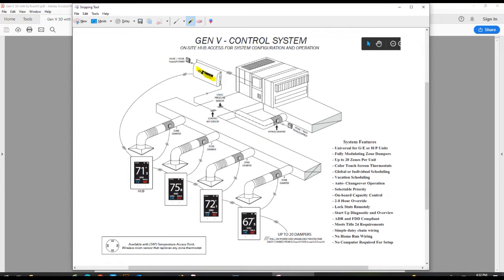Your Gen V control system is powered by an independent 24 volt transformer, and then we daisy chain our 24 volts and our Zonex twisted pair communication wire from the Gen V controller to each zone thermostat and continue daisy chaining that all the way through until you dead end at your last thermostat. The Gen V controller supports up to 20 zones per controller. Each thermostat in turn controls or powers its respective damper. So go ahead and wire in using 18/3 to the damper that it is controlling.